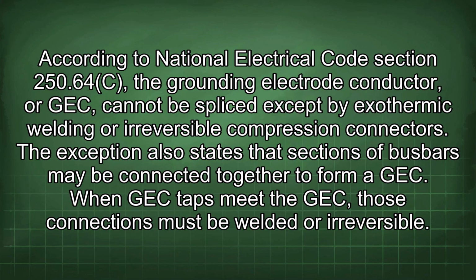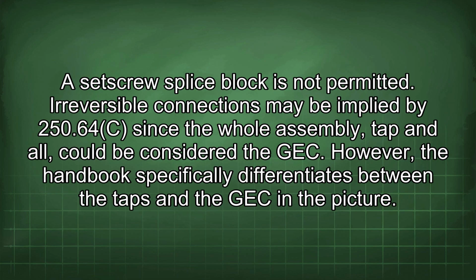According to National Electrical Code Section 250.64(C), the grounding electrode conductor, or GEC, cannot be spliced except by exothermic welding or irreversible compression connectors. The exception also states that sections of busbars may be connected together to form a GEC. When GEC taps meet the GEC, those connections must be welded or irreversible. A set screw splice block is not permitted.